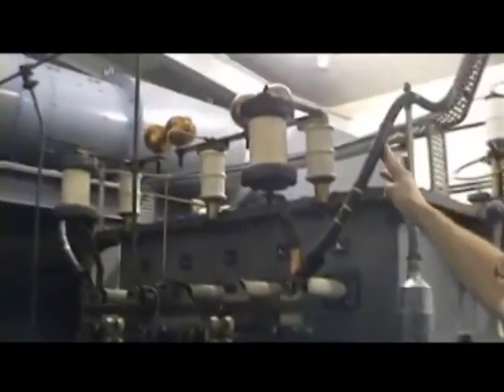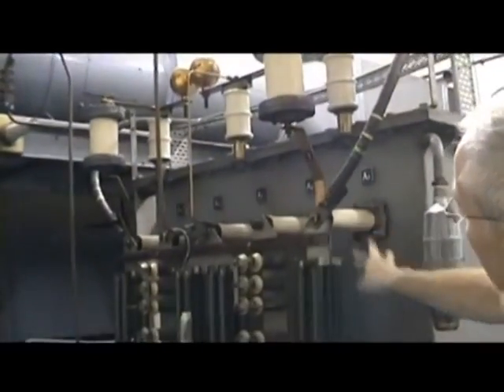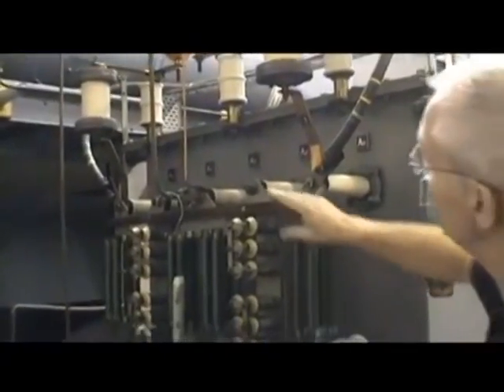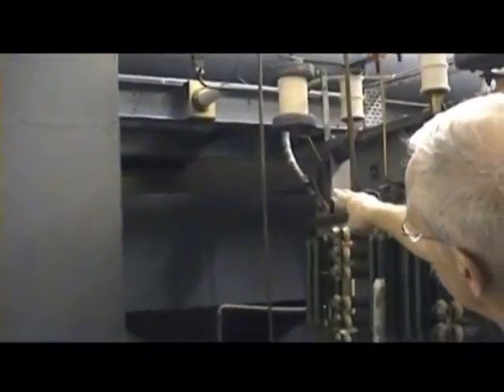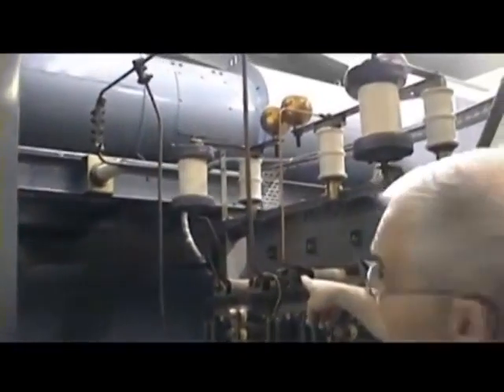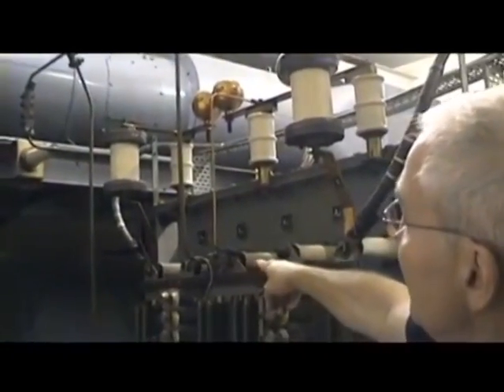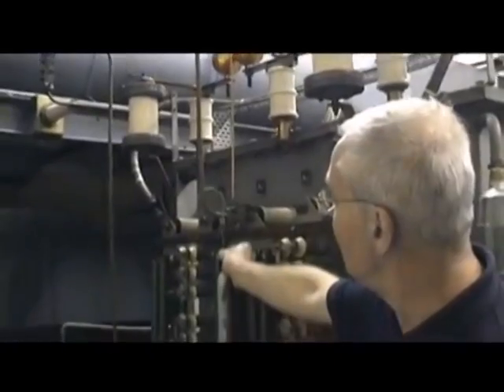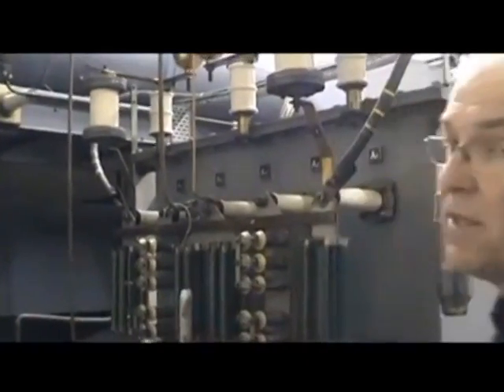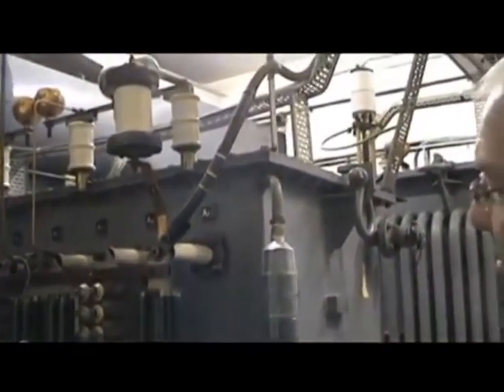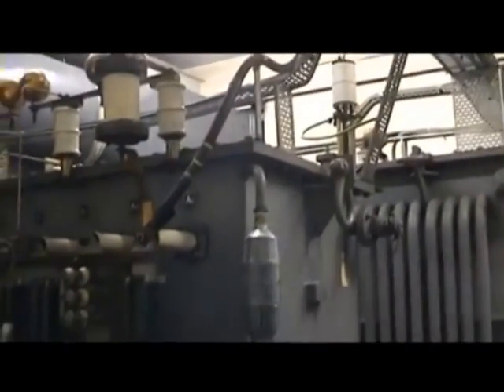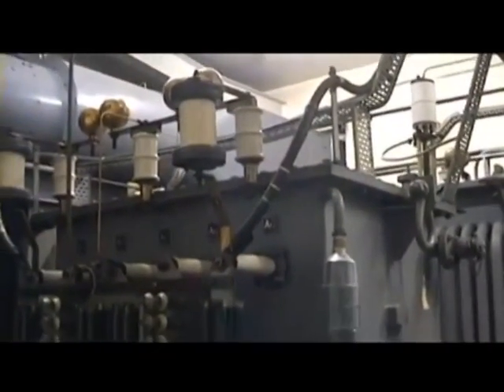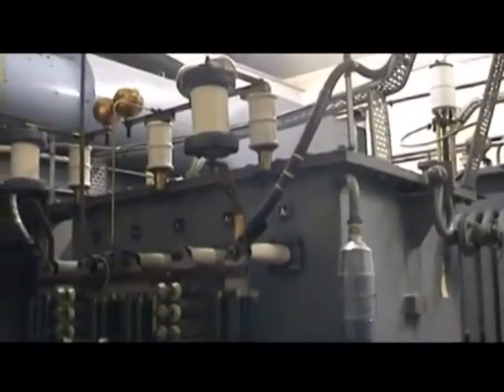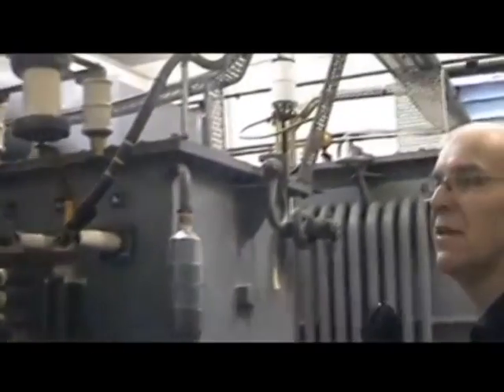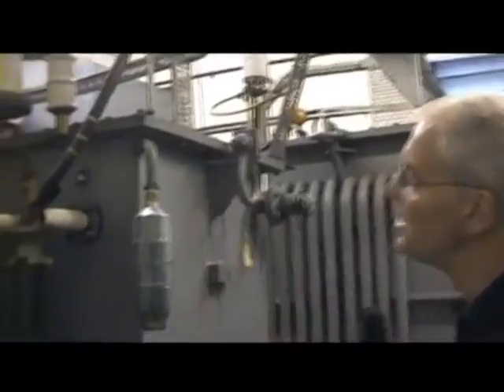The power from the modulator arrives, here's one of them coming in from one of the modulation anodes onto one terminal of the modulation transformer. Across here is the other, and there's a center tap where the 11 kV, 11,000 volts DC starts here. Notice we've got an earth wand on it. If you're watching in the States, it's a shorting stick in your country, but it's an earthing wand in the UK. It's often said that when transmitter staff retire, they hang up their earthing wand. That's one of the standard phrases. So that's the modulation transformer.